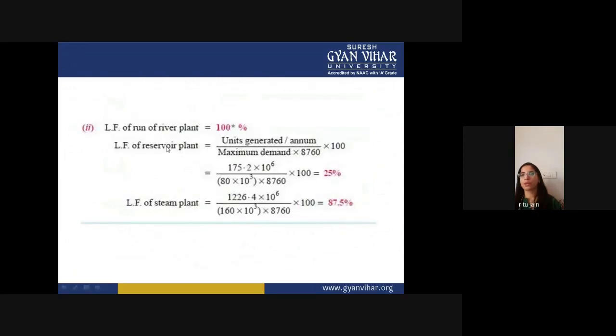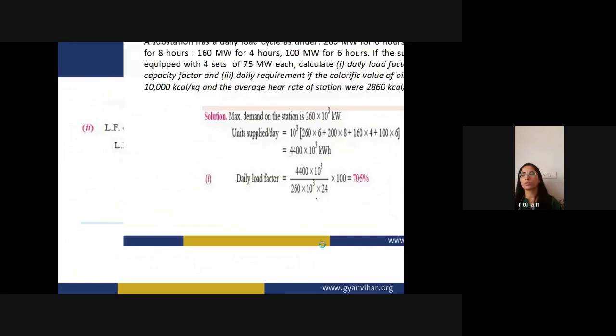Now the load factor of a reservoir plant is units generated divided by maximum demand into 8760. This is your 25%, and the steam plant load factor is 87.5%. So you can compare these three plants and their load factors. The maximum load factor is for the run-of-river plant. After that is 25%, which is for the reservoir plant, and the load factor of a steam plant is 87.5%.